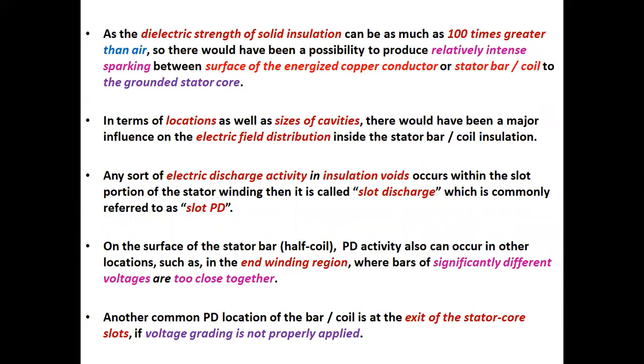As the dielectric strength of the solid insulation can be as much as 100 times greater than air, there would be a possibility of relatively intense sparking between the surface of the energized copper conductor or stator bar or coil and the grounded stator core. The locations as well as sizes of cavities would have a major influence on the electric field distribution inside the stator bar or coil insulation.